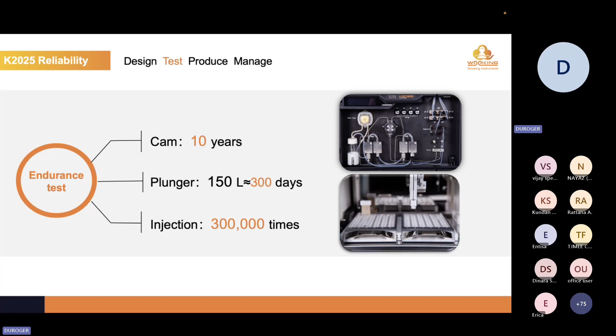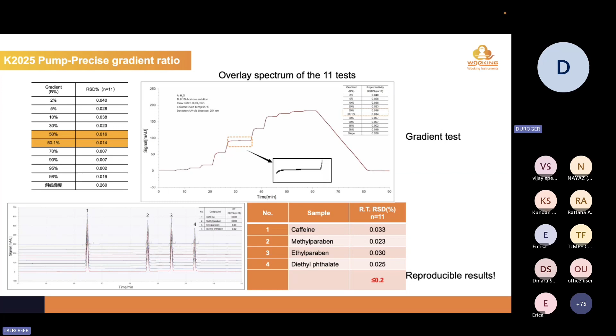And for precision, our best binary pump has very precise gradient differences. We can see 50% and 50.1 percent, there is a sharp gap in the test, and also for different samples like caffeine and methylparaben, it has a very good RSD result. And we have a very unique design of our auto sampler needles, so it makes no difference for different pressures. It's a constant pressure needle.